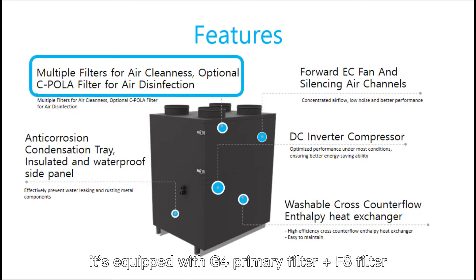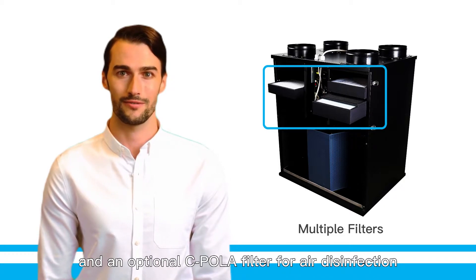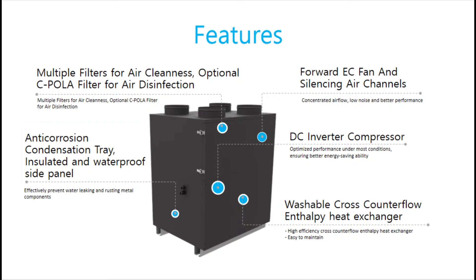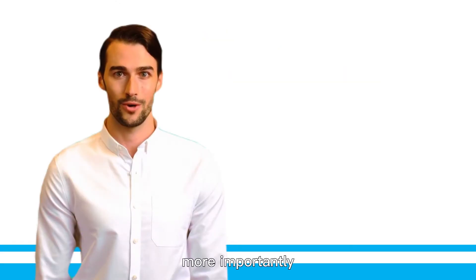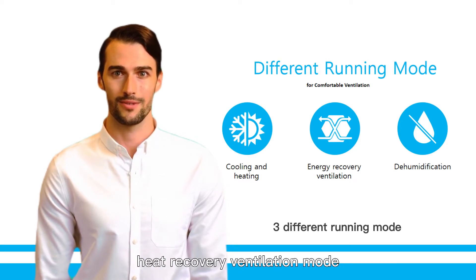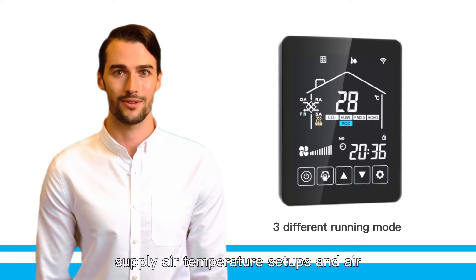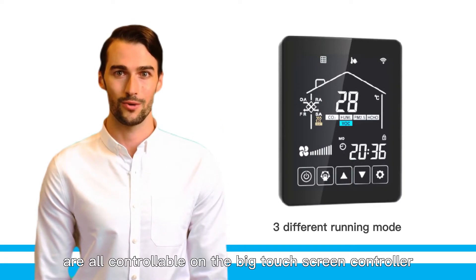Fourthly, it is equipped with a G4 primary filter plus F8 filter, and an optional C-POLA filter for air disinfection. The anti-corrosion condensation tray effectively prevents water leaking and rusting of metal components. More importantly, all functions — including cooling or heating mode, heat recovery ventilation mode, dehumidification mode, supply air temperature setups, and air volume adjustments — are all controllable.